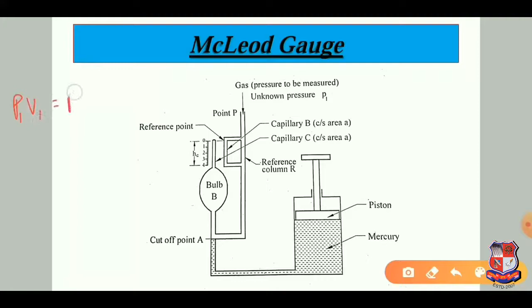So in the McLeod gauge, a known volume V1 of gas sample at unknown pressure P1 is trapped and then isothermally compressed to P2 V2 by means of a rising mercury column. This amplifies the unknown pressure P1 to P2, and P2 is measured by manometric means, which means P1 is equal to P2 into V2 divided by V1. So we can measure the unknown gas pressure. The construction of the McLeod gauge is shown in the figure.